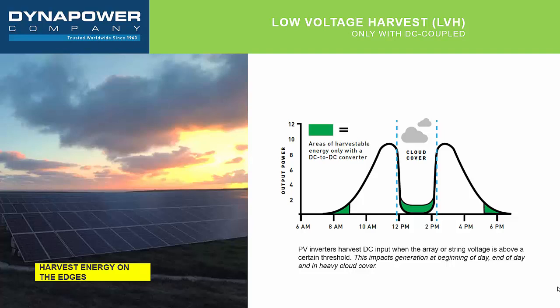That is the voltage that the PV inverter needs to see in order for it to operate. And to put some rough numbers on this, for a typical 1500 volt DC PV bus, that inverter wake-up voltage might be somewhere between 800 and 900 volts DC. So any time that the PV inverter has a voltage, but it's below that 800 or 900 volts, that's essentially lost power. And as soon as you put on a DC coupled storage system, you are now able to charge your batteries using that energy below that threshold wake-up voltage. This could be in the beginning of the day, the end of the day, or even during a period of cloud coverage in the middle of the day.